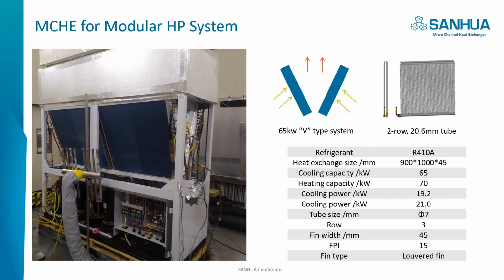We designed the 2-row 20 mm microchannel design, still with 4 coils to replace the original 4 fin tube heat exchangers. This table shows the parameters of the system: refrigerant, heat exchanger size, which is the same, cooling capacity, heating capacity, and the fin tube heat exchanger parameters.